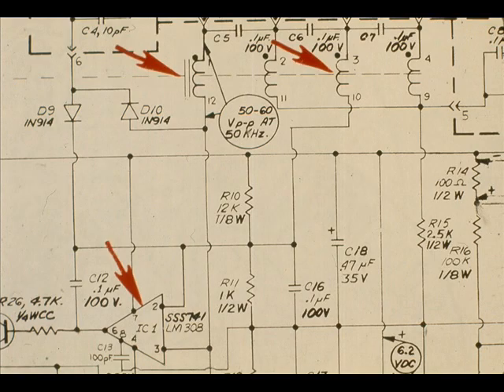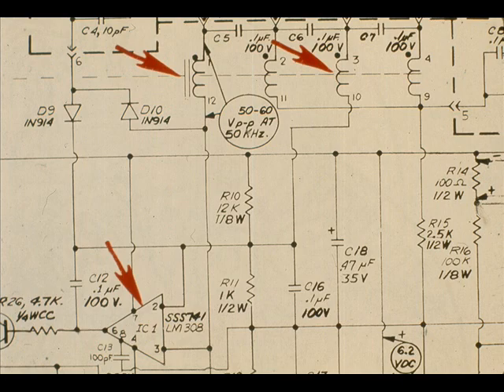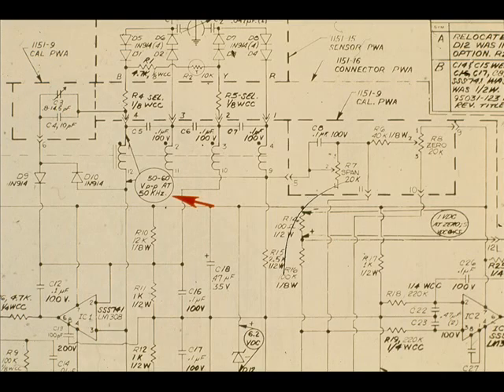The output currents through transformer windings 1–12 and 3–10 are compared in operational amplifier IC1, and the output is fed to the oscillator control circuit. Since the sensing element capacitance is variable with the applied differential pressure, the oscillator frequency also varies about the normal 50 kHz.